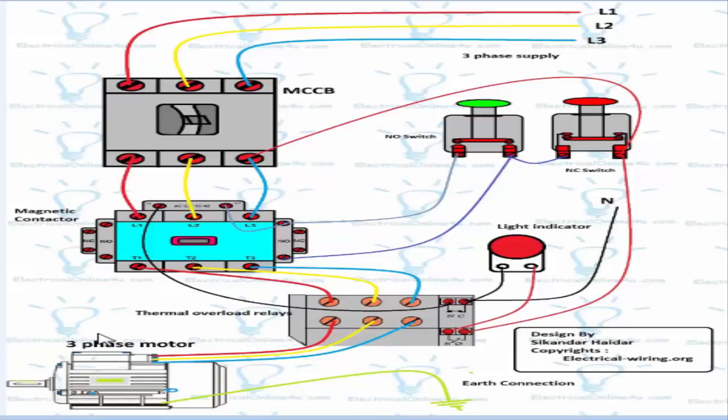In case of over current flow the thermal overload relay bimetallic strip expands and converts this NC to the NO and NO to the NC. Here we will open connections so the contactor will de-energize automatically, and here we will close connections so this light indicator will be on.